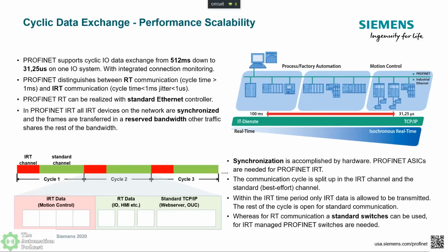And as I said before, for PROFINET RT, any standard switches can be used. You can go to Best Buy and buy a standard switch. You can use that for PROFINET RT communication, but for PROFINET IRT, managed PROFINET IRT switches have to be used. Okay.